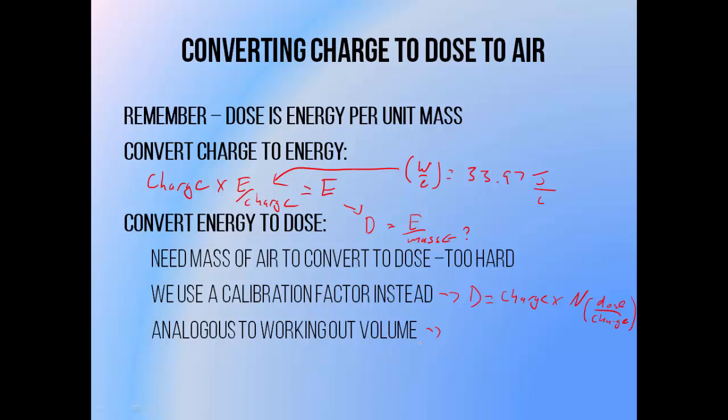Converting a cobalt-60 appropriate calibration factor to one that's applicable to our own beams is the main reason why we need dosimetry codes of practice, like TRS-398. I'm going to be covering how we can use a dosimetry code to do this in a separate video.